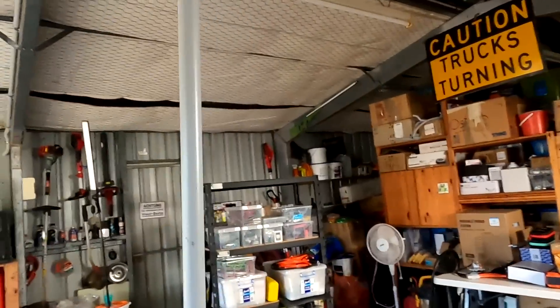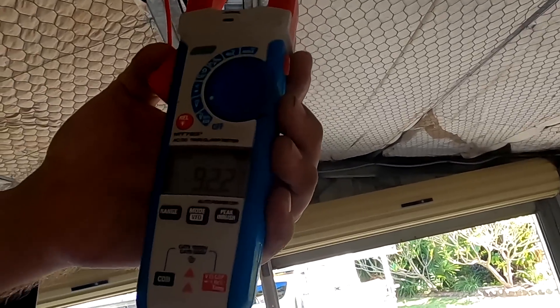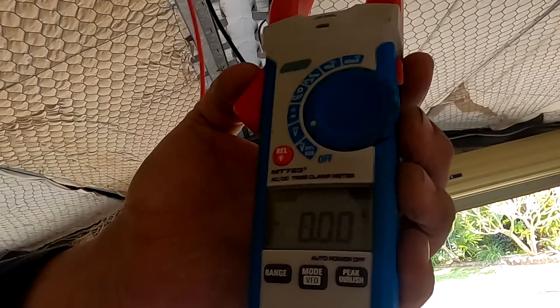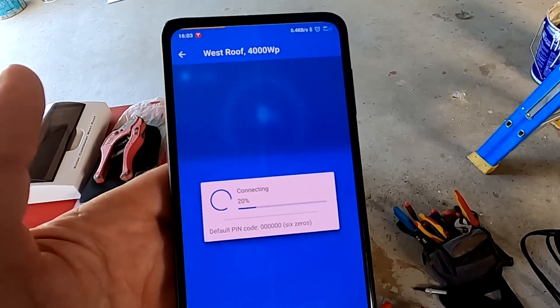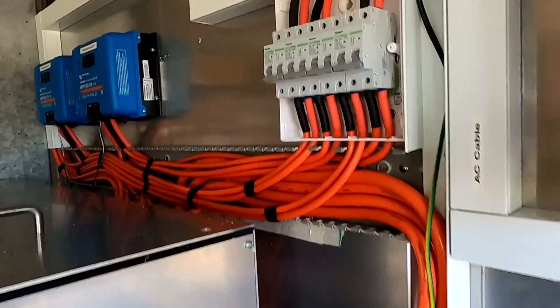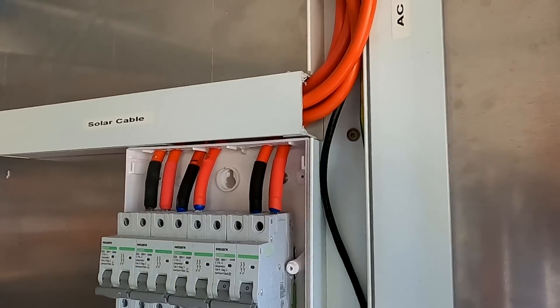Polarity and voltage is good up there. Do I need to check it? That's string 4 - 92. Nice. String 4. String 3. Here comes the big moment. Chris is chucking in all the fuses. Second from the left should be your solar voltage incoming.